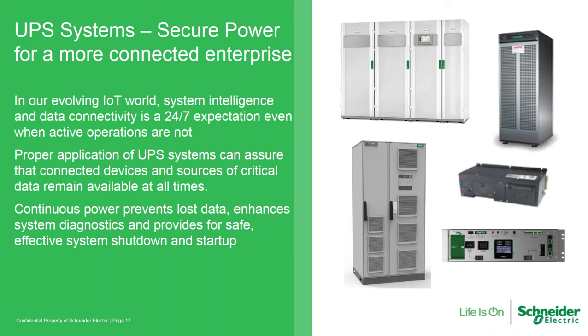Systems don't start up. The example we use is if you have a 4-second power blip, chances are you're going to have a much more substantial outage than 4 seconds, just because of what it takes for the systems to come back online. And in a lot of cases, those systems require intervention, not simply the power coming back on.